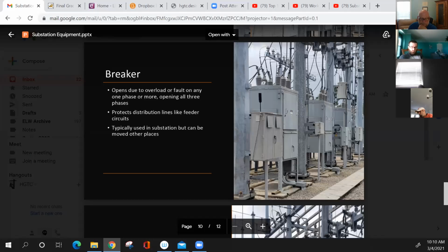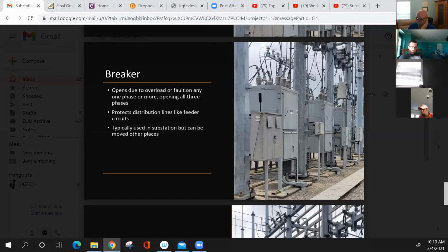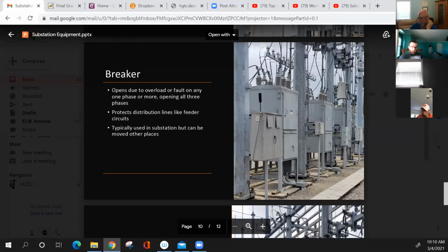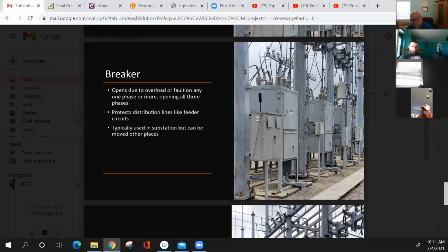No, that ain't it. I don't have it. I canceled it out. But anyway, good piece of equipment, like I said, but lots of faults can take them out. You can put it on hotline tag when you're working out in the field, like you're changing out a pole or you're moving some phases of ground, and you don't want it to operate those 3 times. You just want it to go through that quick operation, that first one. And then you want it to go right out if something happens.